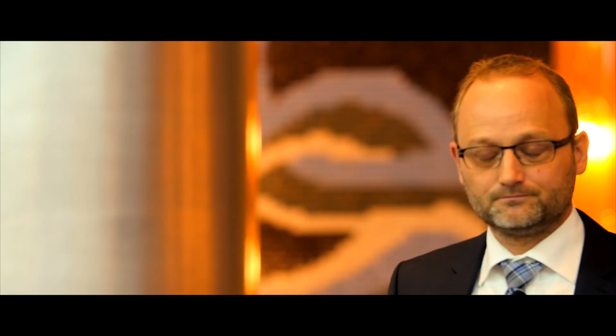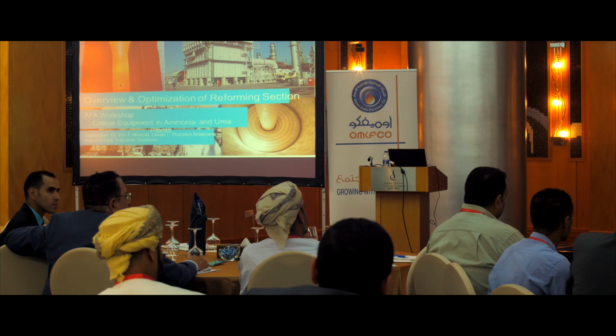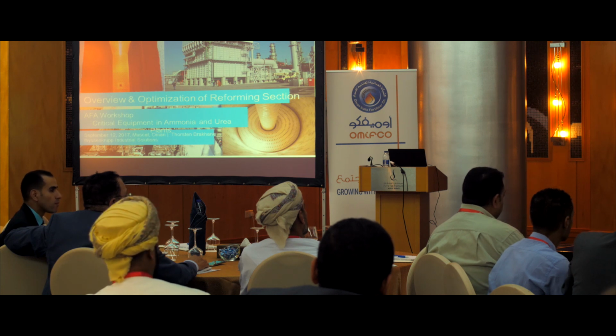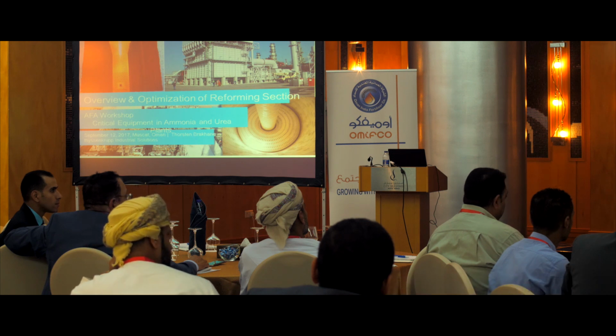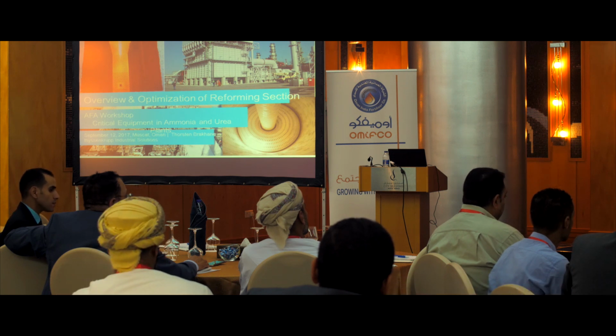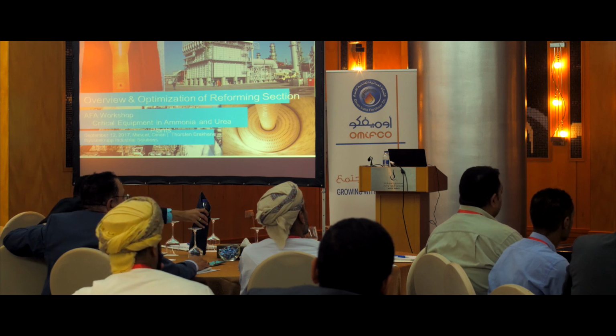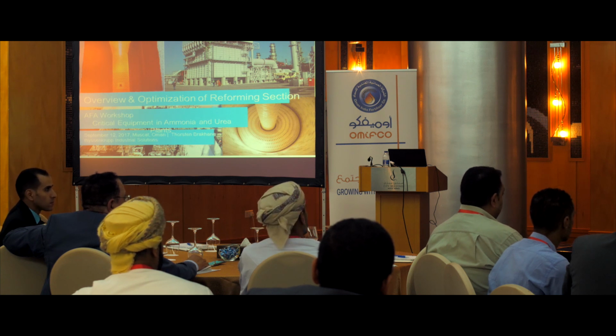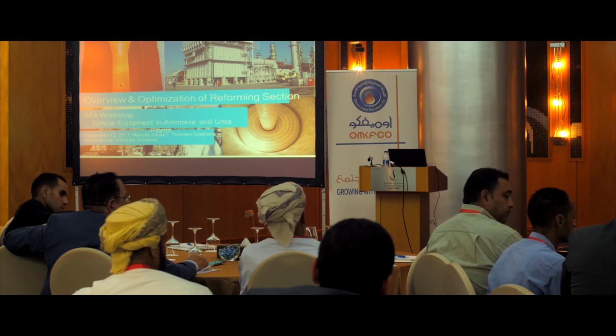So how do you detect it? You will find ammonia coming out of the stack. In the stack you have, of course, a CEMS system, which is measuring the NOx, CO, and also ammonia. So if there's a leakage in the convection bank, you will see it at the measurement system. In this case, you will have to shut down, fix the leakage, and then start again, right? Right, yes, but we didn't have that problem so far. I'm not aware of any problem within the convection bank, because you don't have any flanges there, just a welded pipe and a screwed-in nozzle, so normally there is no potential for leakage. Okay, another question, please.